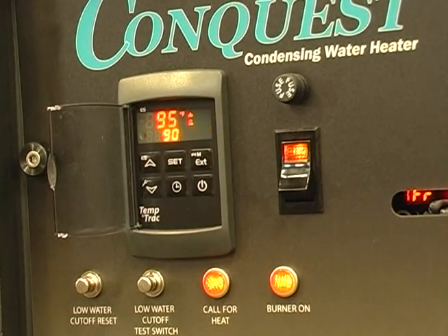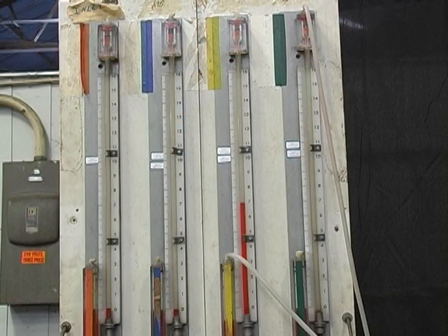With the burner firing, measure the flow gas pressure at the beginning of the gas train. If flow gas pressure is equal to or greater than 3.5 inches water column, continue with the startup. If the flow gas pressure is less than 3.5 inches, contact PVI immediately for instructions on how to correct the situation.